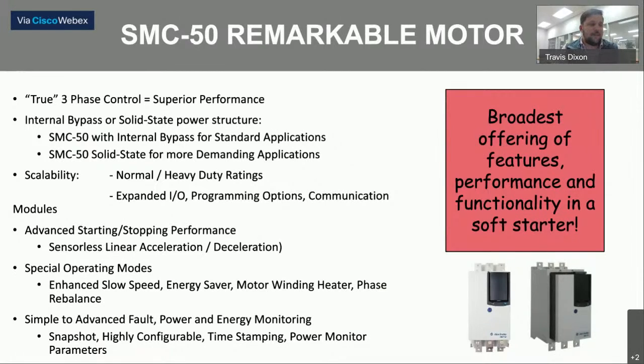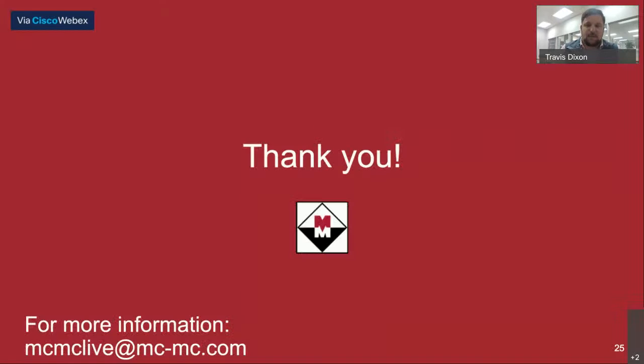Also, the high fault SCCR ratings with standard breakers. It'll fit great with non-traditional applications, you know, transformer, linear induction, resistive heating applications, and also the ability to mitigate having to have additional power monitors, scopes, ETMs, motor winding heaters, or a DC brake. And that is all I got.